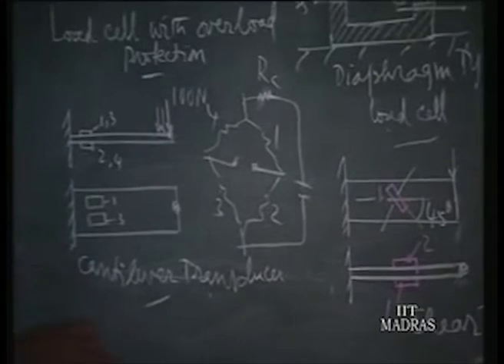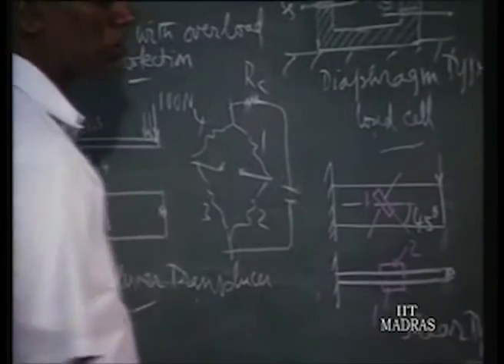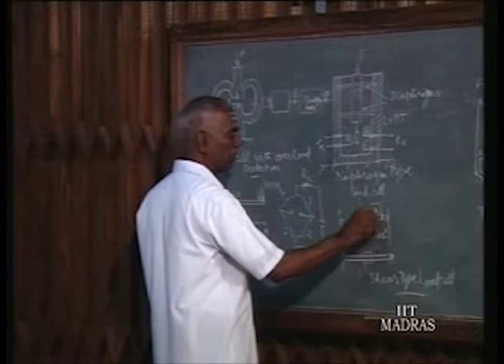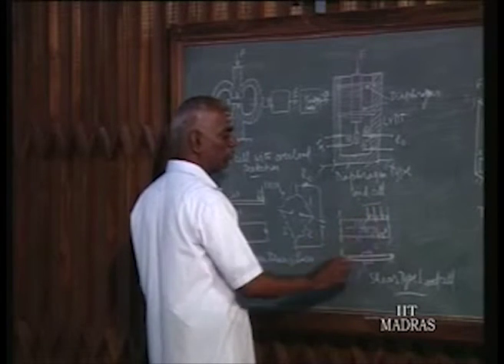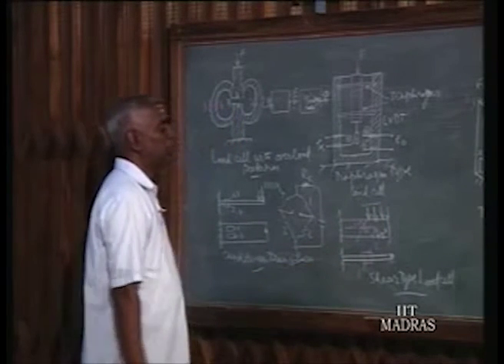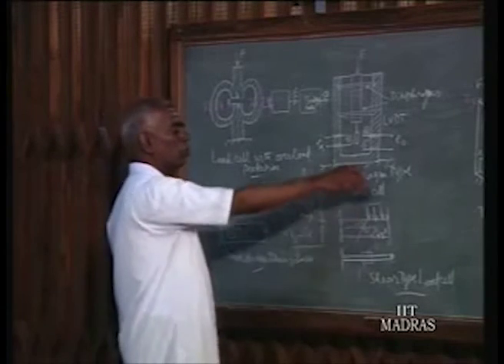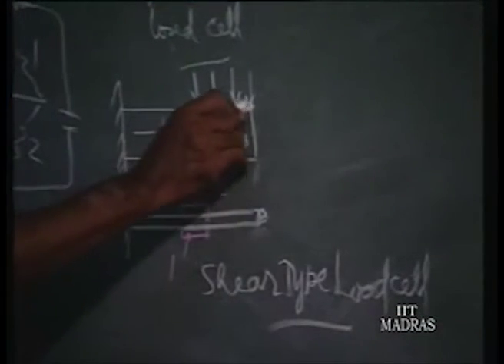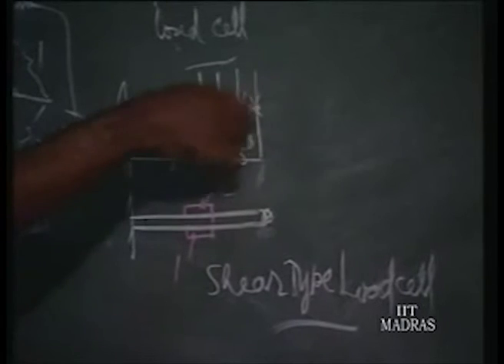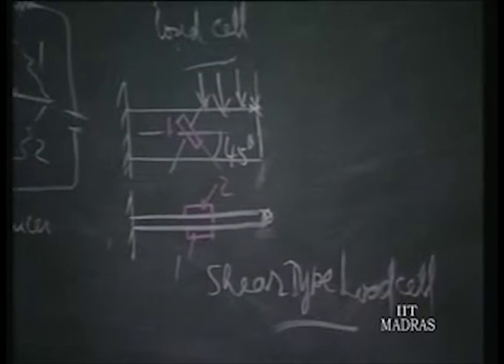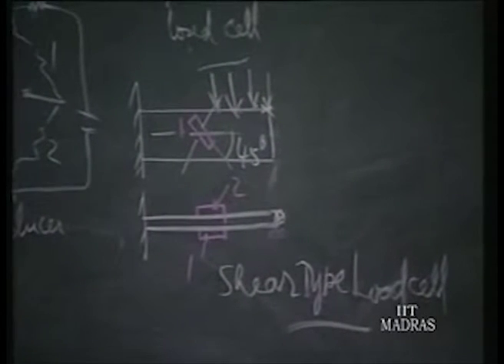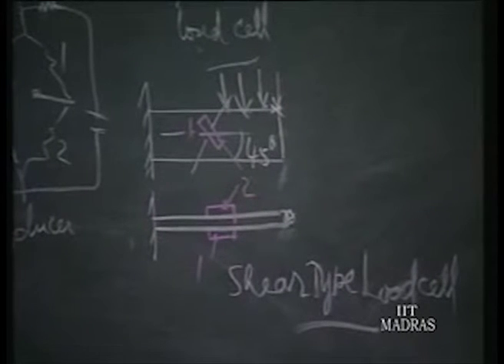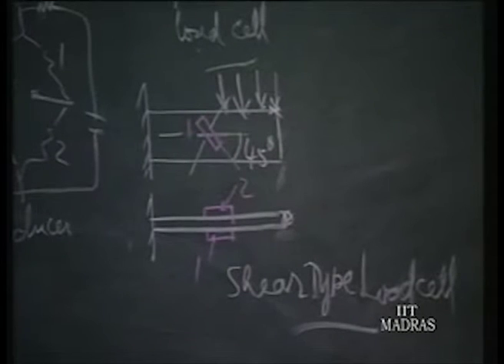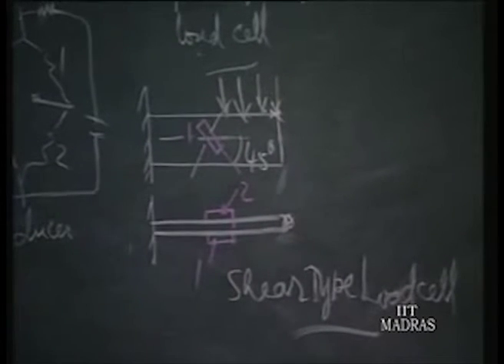That problem is solved once you go for the shear type of load cell. Here you can apply the load here or here, nothing will happen. It will give the same reading. It is non-sensitive to the location of the load about the loading point. If you vary it, it does not affect the instrumentation, whereas in the cantilever type it is very sensitive to small errors in applying the load. How is it non-sensitive? It is because this instrumentation is based on shear.